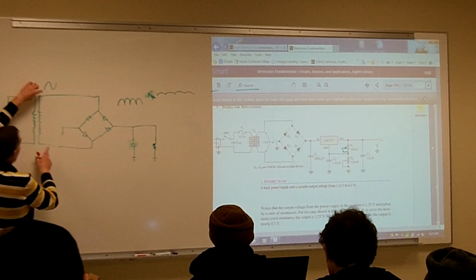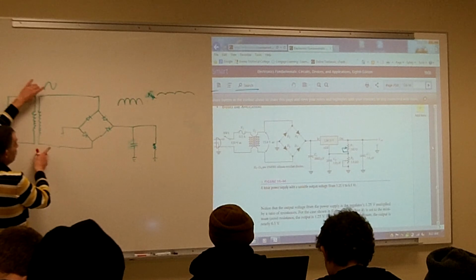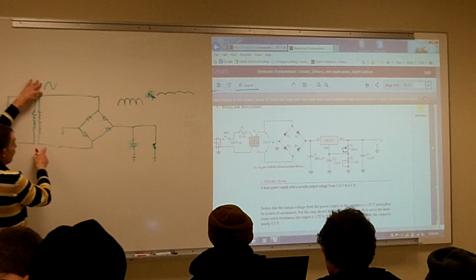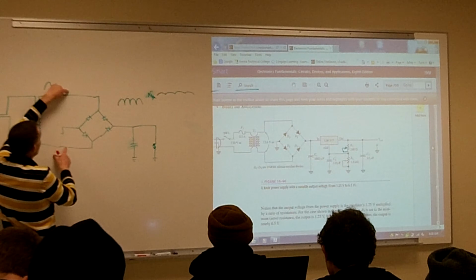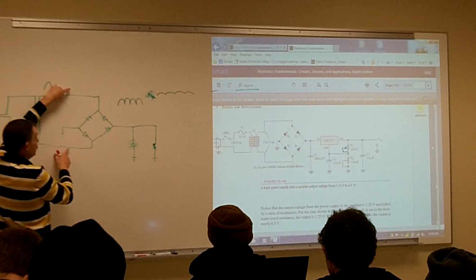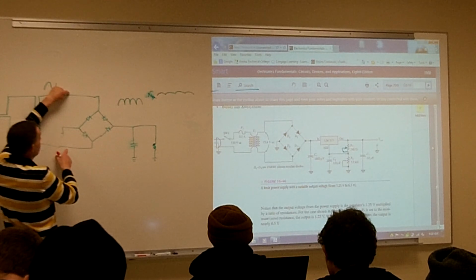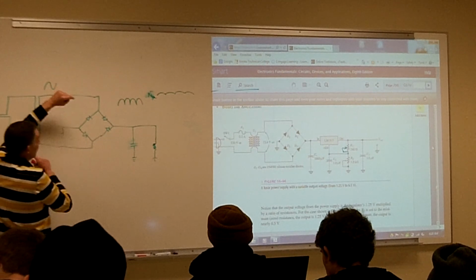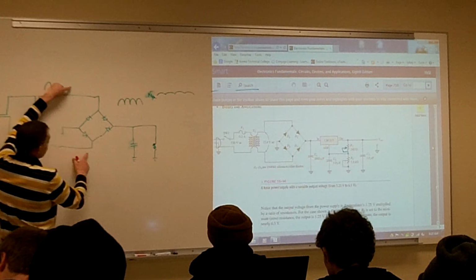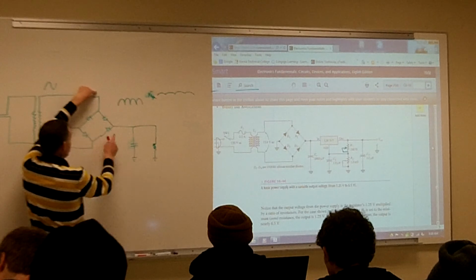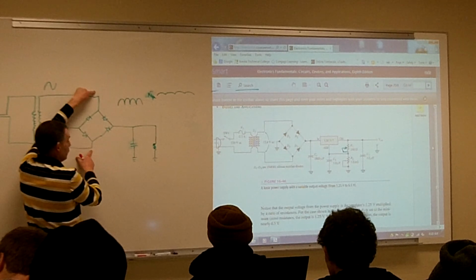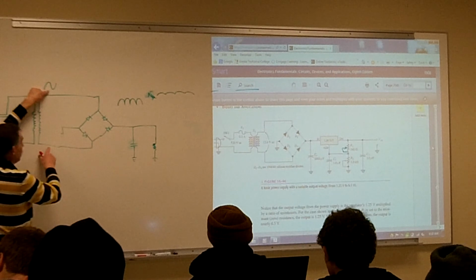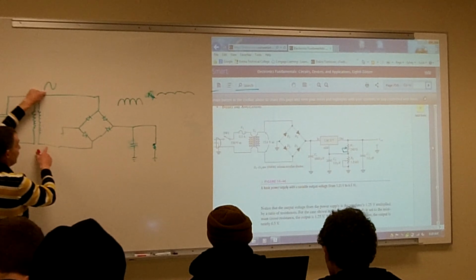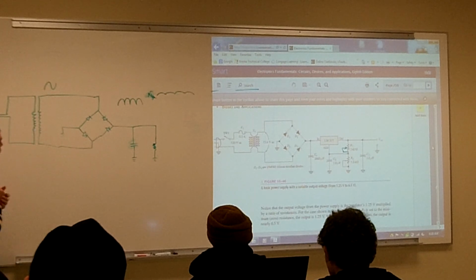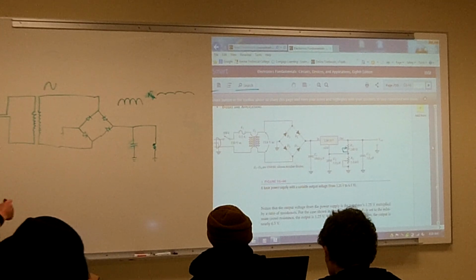So now measuring the secondary of your transformer. What do I need to do to measure my voltage across my secondary using my oscilloscope? Here's my secondary. My grounds are here, but I'm not referencing it to my ground. I'm measuring from my two hot wires coming out of the secondary. What do I need to do to measure my voltage properly, and how do I need to set up my oscilloscope for that?